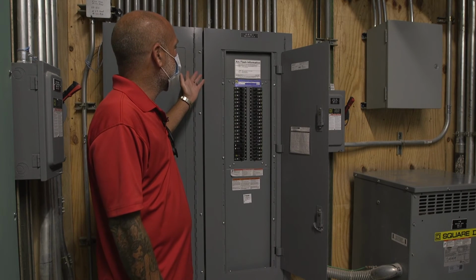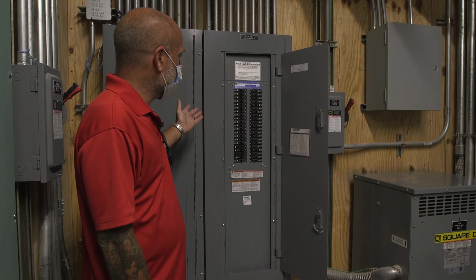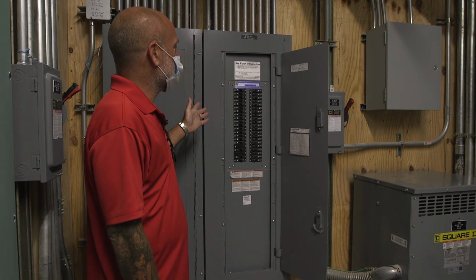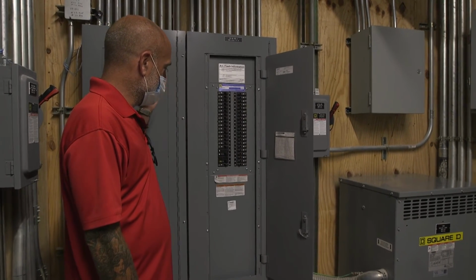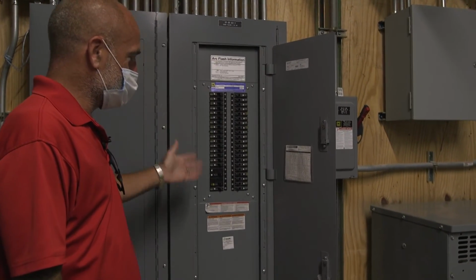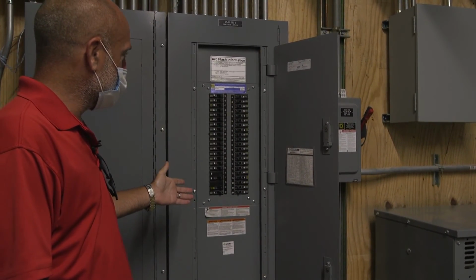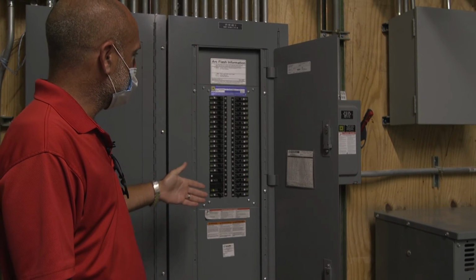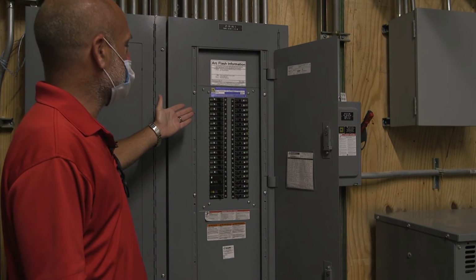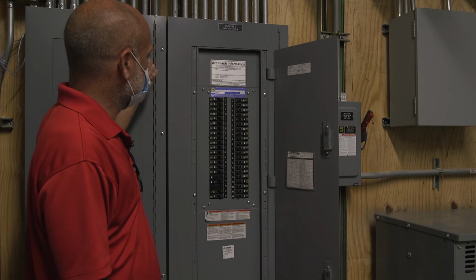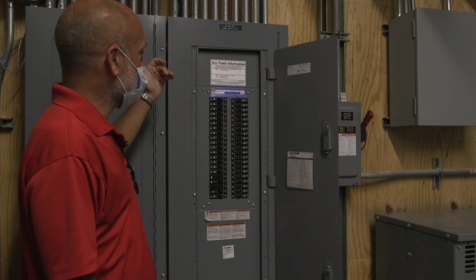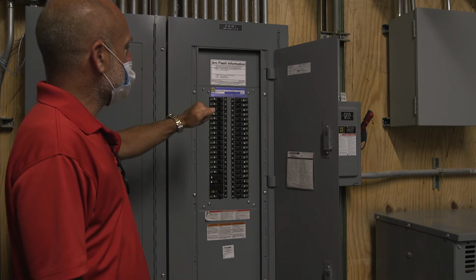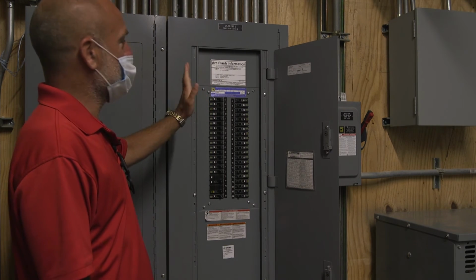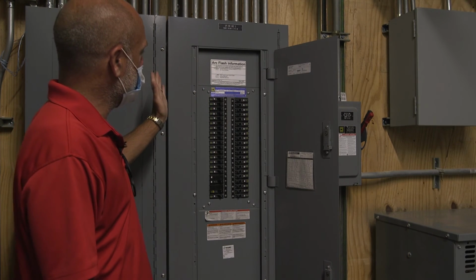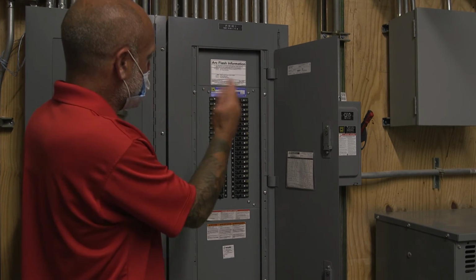This is a Square D NQ panelboard. Pretty much load distribution. Could be main lug, main breaker. This one happens to be a main lug. So the main feed's coming in, distributing the power to the circuits in the building. Circuit breaker operation, once again: on position is all the way to the right, trip would be in the middle, off would be to your left.